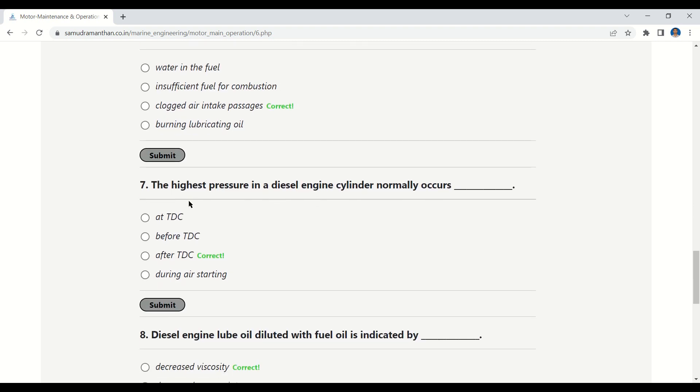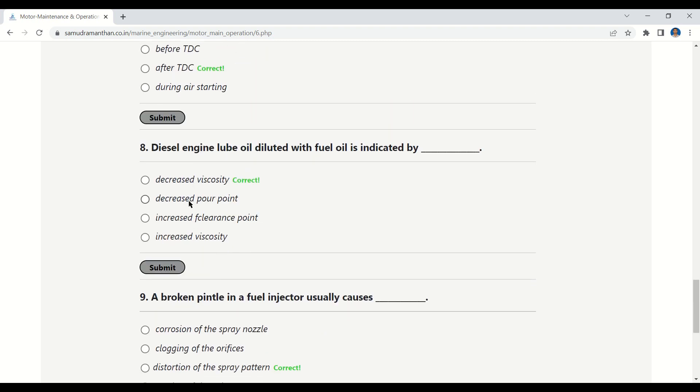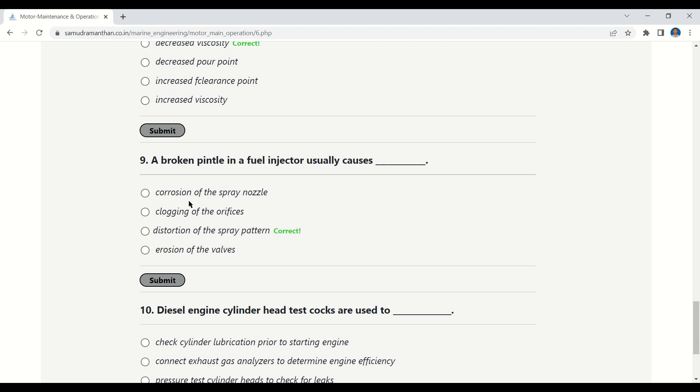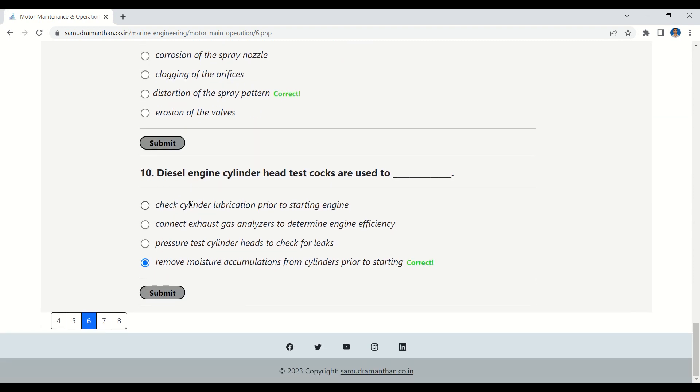The highest pressure in a diesel engine cylinder normally occurs after TDC. Diesel engine lube oil diluted with fuel oil is indicated by decreased viscosity. A broken pintle in a fuel injector usually causes distortion of the spray pattern. Diesel engine cylinder head test cocks are used to remove moisture accumulation from the cylinder prior to starting.